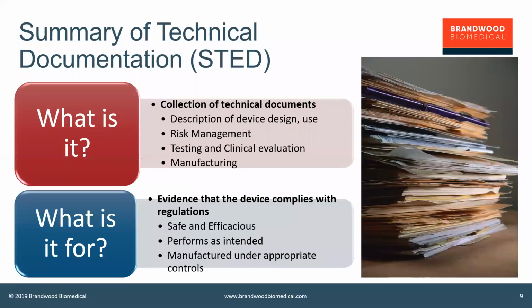Okay, so we've talked about DHF and DMR. One other document that comes up, especially in regulatory submissions, is the STED. And the STED is the Summary of Technical Documentation. So what is that? It's a compilation or a collection of technical documents. It's not full technical documents. No, this is a key aspect of the STED. It's really meant to be the summary document so that a regulator can get a very good picture of the design and development and any verification and validation activities that you've completed for your device in one simple location.